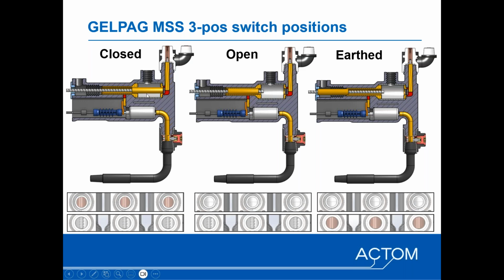So on the left-hand side, we've got the moving contact in the closed position. It's driven by a spindle mechanism and a tubular moving contact. In the middle, it's in the open position, and then on the right-hand side figure, the moving contact is moved to the left, which is the earthing position, and the corresponding view you see through the operating windows is shown at the bottom.